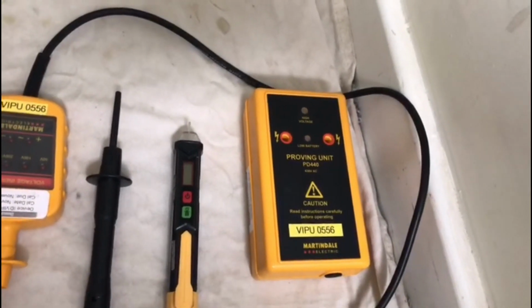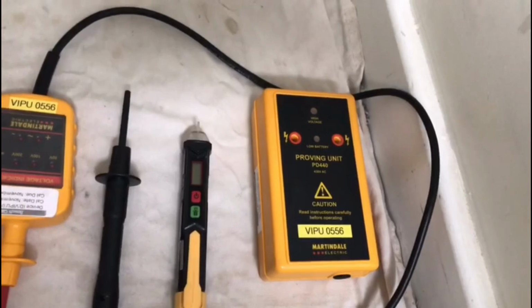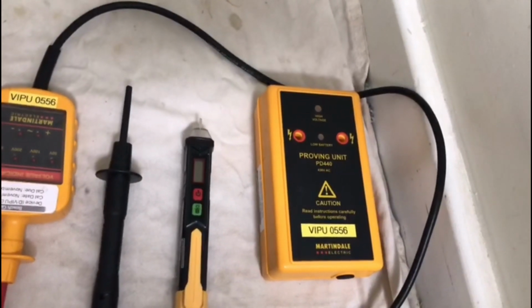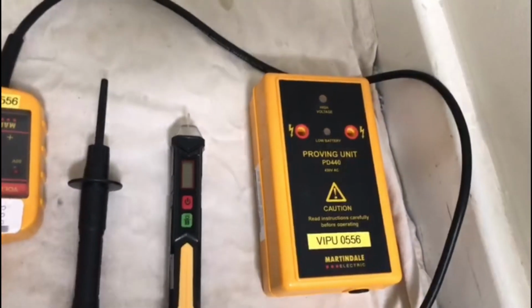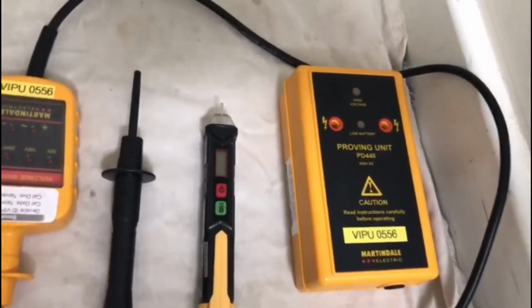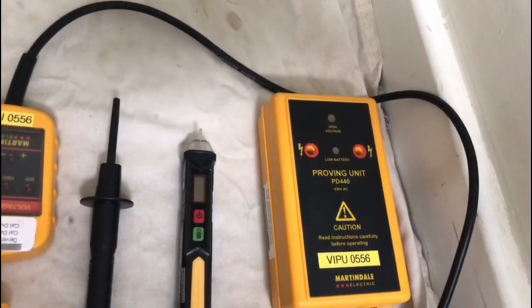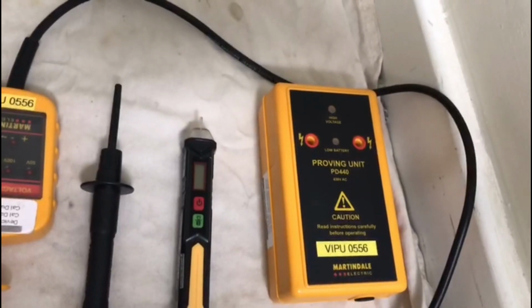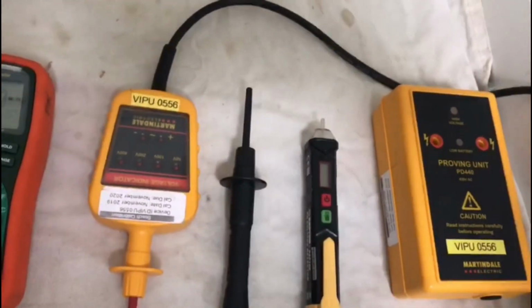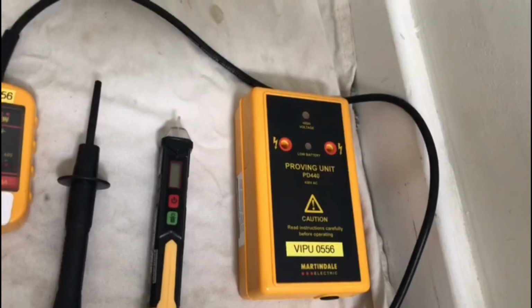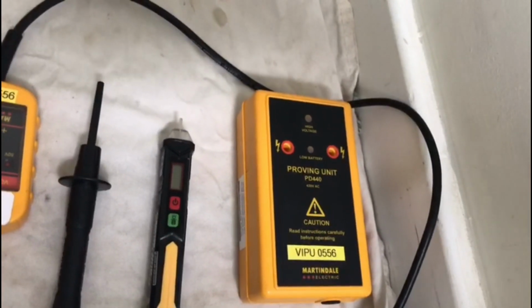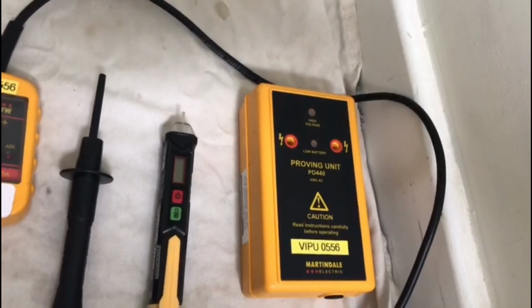The last piece of kit I use is a proving unit. Basically you can prove something which you know is live. If you're unsure whether something is live or not, you can use a proving unit. This is a powered unit, with a 9-volt battery inside it, and you can test your testing equipment with it. Normally I use it to test a voltage tester. You use your proving unit just to test that, so that you know your equipment's working properly.